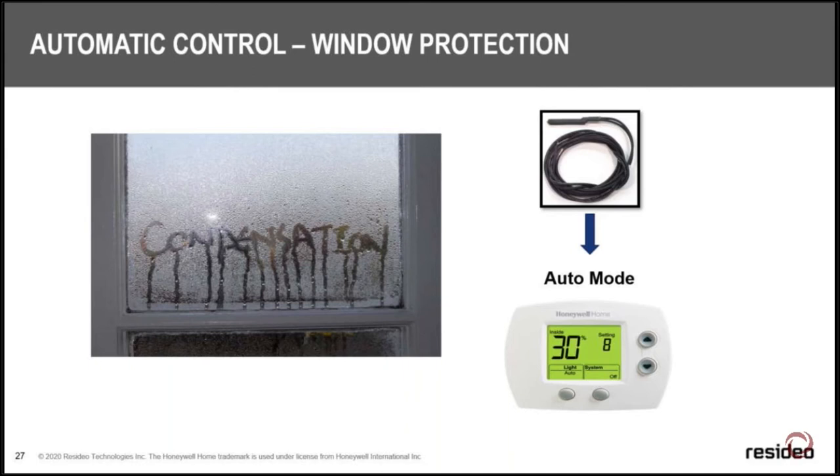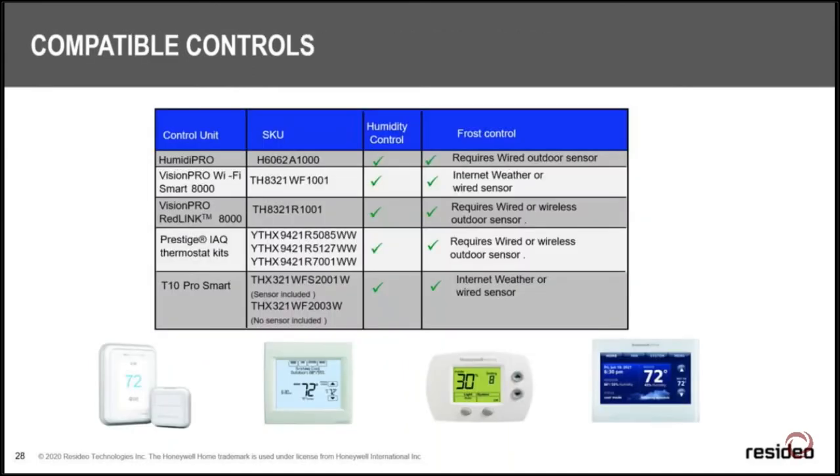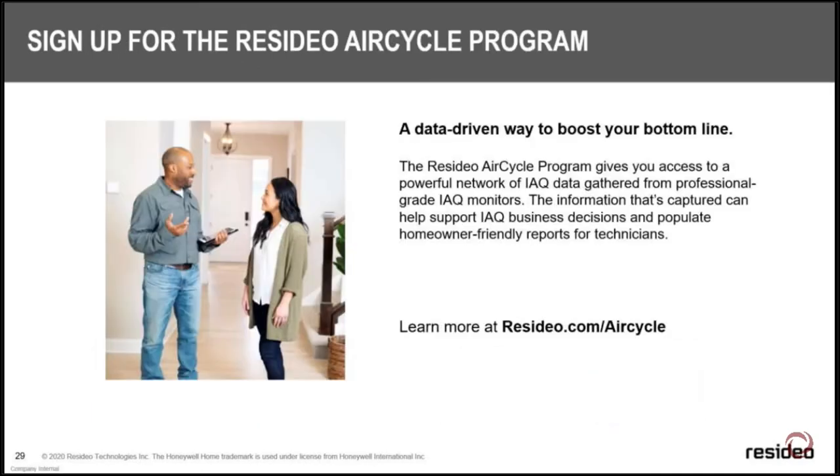We also have the Prestige IEQ, the RedLink VisionPro 8321R, the Wi-Fi VisionPro, and the T10 that can run a humidifier as part of your thermostat system. The Prestige gives you three IAQ device outputs — you can run the humidifier, dehumidifier, and ventilator from one device. The RedLink 8000 without the EIM allows one assignable IAQ output: humidifier, dehumidifier, or ventilator. The T10 also has one assignable output for humidifier, dehumidifier, or ventilator.